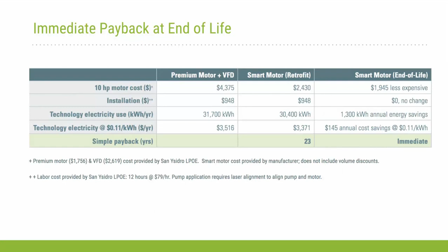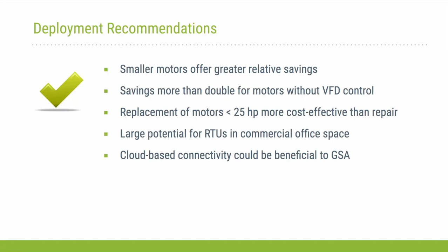In terms of deploying the smart motor technology, smaller horsepower motors offer the greatest relative savings, as we saw with the ORNL demonstration, where savings were on the order of 33 to 70%, versus the pumping application at San Ysidro, where it was on the order of 4 or 5%. Savings can more than double when replacing a motor without a VFD with the smart motor. Another opportunity is, since there's a large number of RTUs in commercial office spaces, there's a large opportunity to deploy a smart motor in HVAC fan retrofits. And finally, the cloud-based connectivity and fault detection capabilities of the smart motor could be beneficial to the GSA.